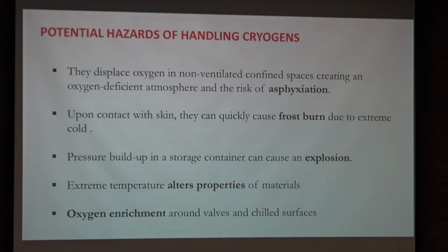When this pipe gets cold, you can actually get condensation of oxygen from the air on the pipe, because these substances have a boiling point that's below the boiling point of oxygen. So on the outside of the cold pipe, even if your cryogen is properly enclosed, you can still get oxygen enrichment, and that could potentially create a fire hazard or explosion hazard, because oxygen is of course quite combustible. So these are the main dangers when handling cryogenics.